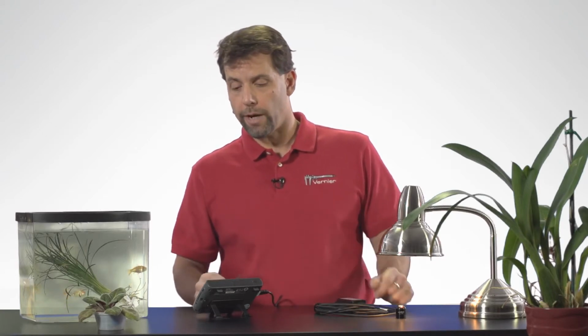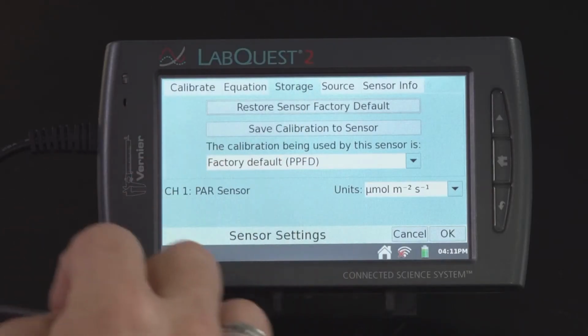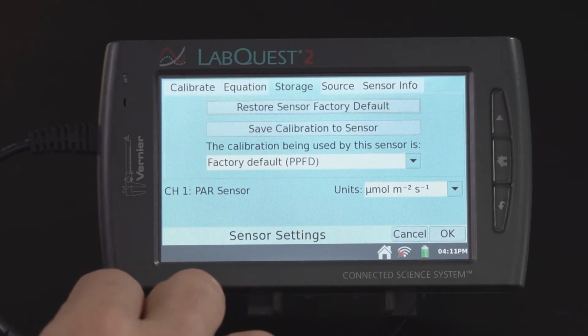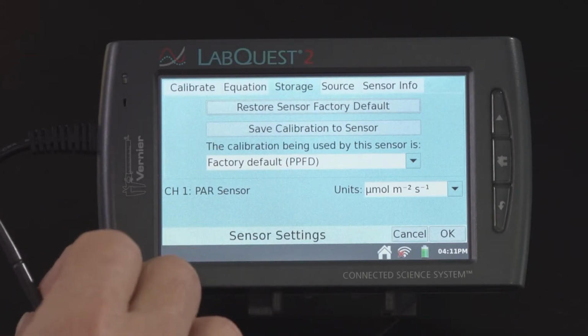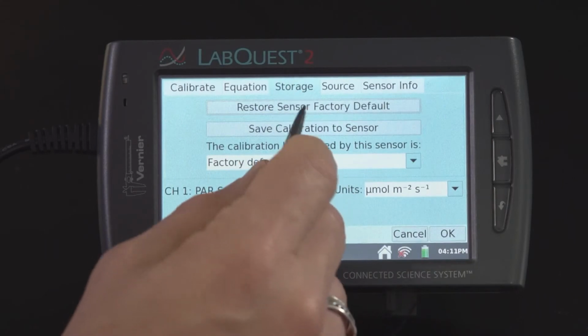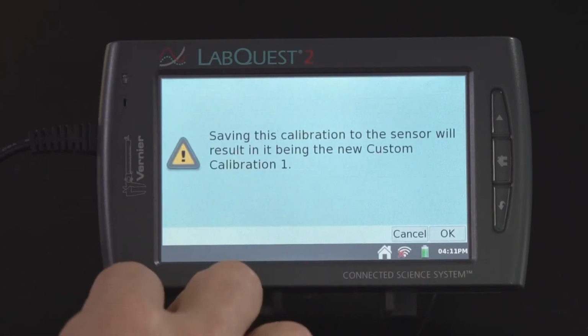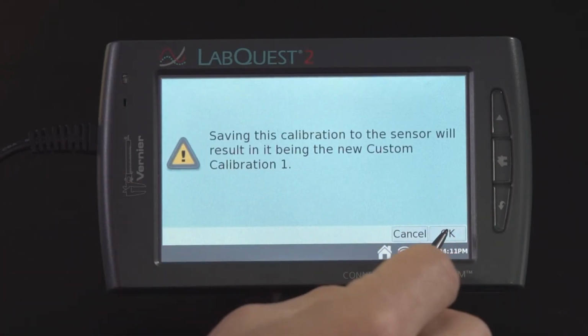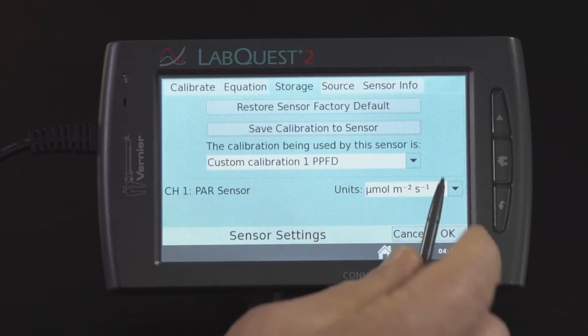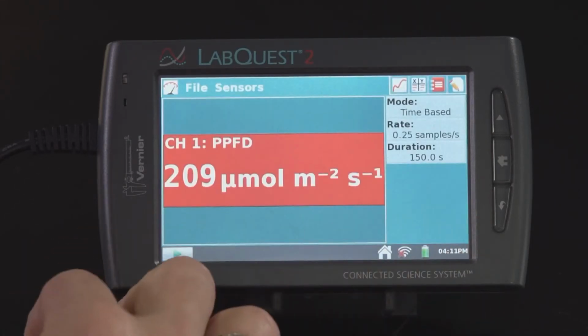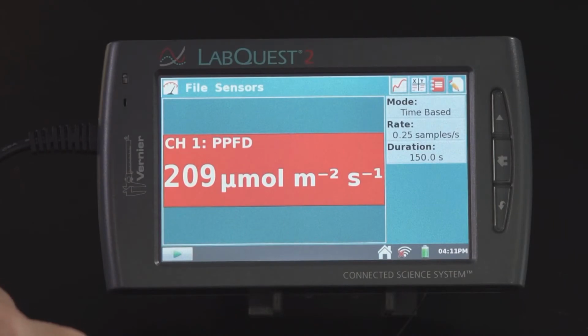Now, what's really nice is if you want to go back and restore it, all you would have to do is select Restore Sensor Factory Default, and then you're using the calibration for outdoor use. So I'm going to save the calibration to sensor and say OK. And now it's reading 209.